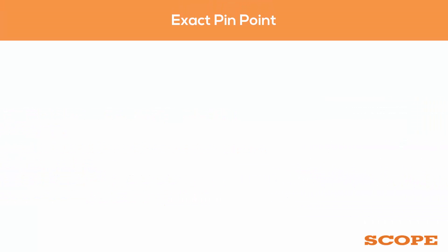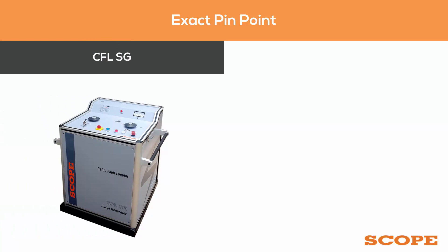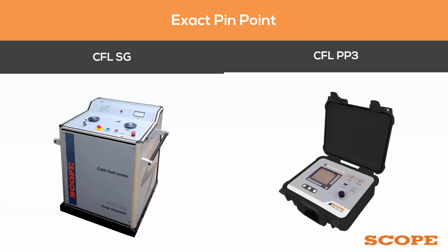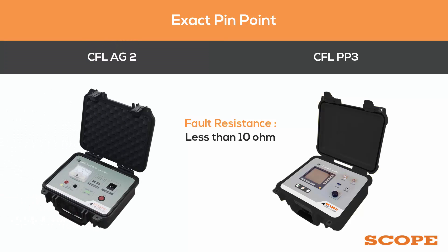After route tracing is completed, the exact pinpoint of the fault must be determined. This can be done using CFL SG with CFL PP3 if the pinpoint fault resistance is more than 10 ohms. If the pinpoint fault resistance is less than 10 ohms, CFL AG2 with CFL PP3 can be used.